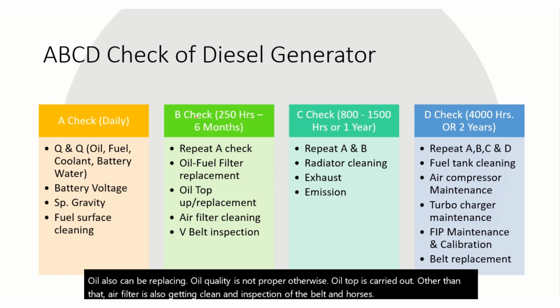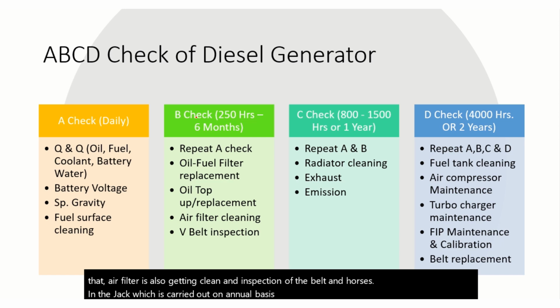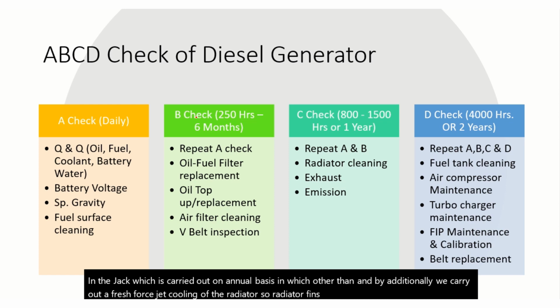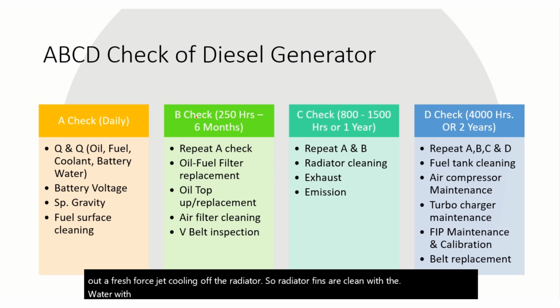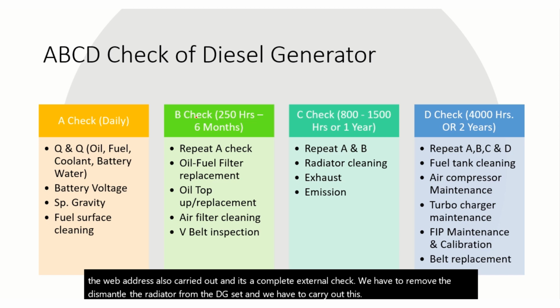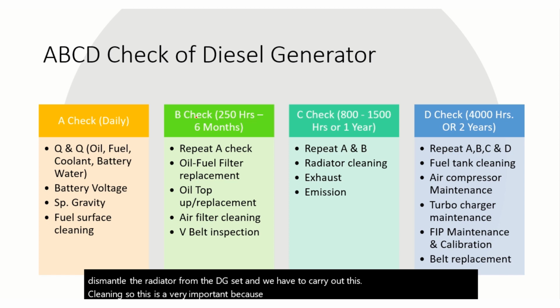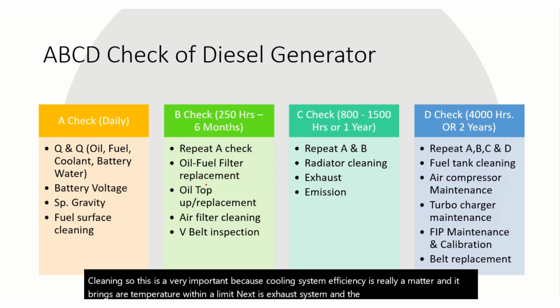In the C check, which is carried out on an annual basis, other than A and B, additionally we carry out a force jet cleaning of the radiator. So radiator fins are cleaned with water with the force jet, so that all the choking in the radiator fins is removed. Inside flushing of the radiator is also carried out, and it's a complete external check. We have to dismantle the radiator from the DG set and carry out this cleaning. This is very important, because cooling system efficiency really matters and it keeps our temperature within a limit. Next is the exhaust system, and the last one is the emission.